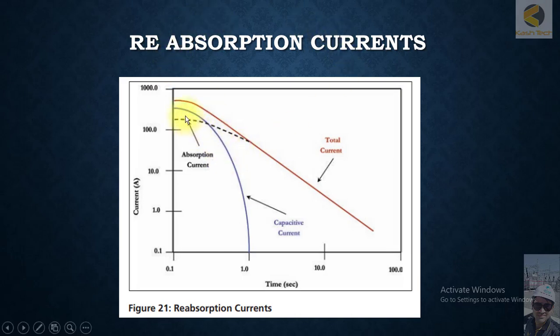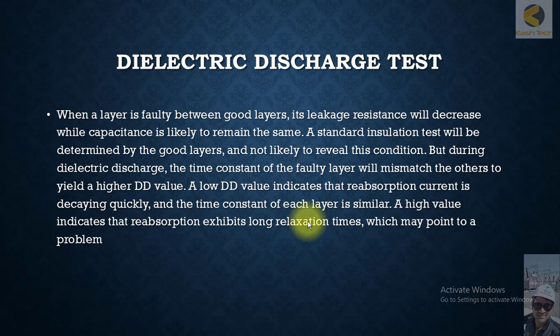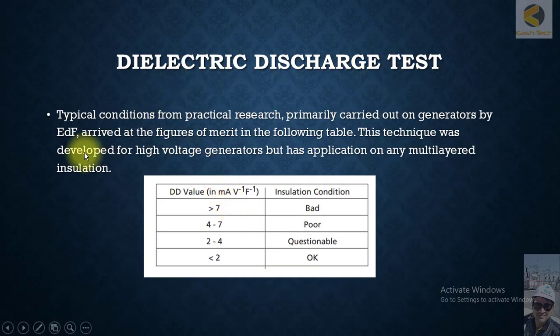Here is the reabsorption current — you can see the absorption current, the total current, and the capacitive current. After some time, the capacitive current has decreased, but the absorption current is still there and will take much longer to decay. You can consider different layers as different capacitors connected together. If all capacitors are healthy, you will get fast discharge and fast decay. But if one of the capacitors — one layer — is not healthy, then the discharge will be slower, meaning that one layer of the insulation is not healthy.